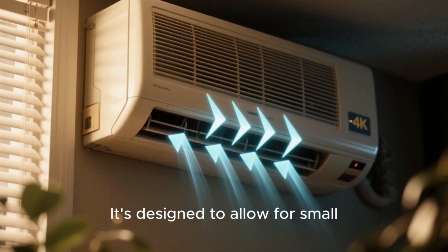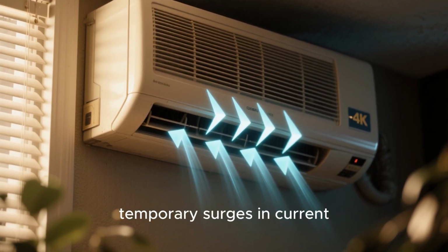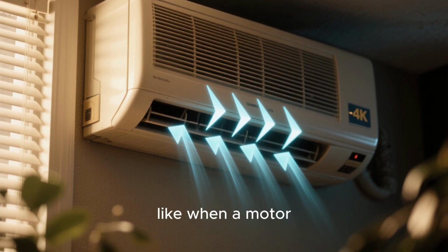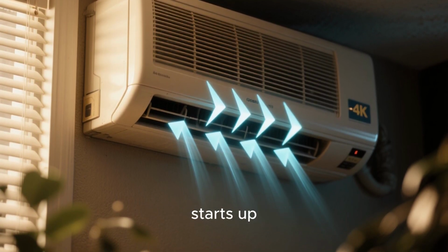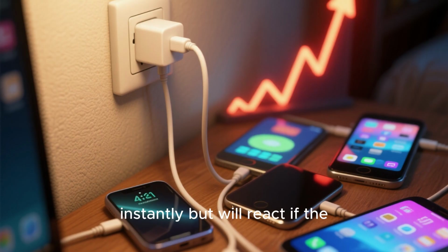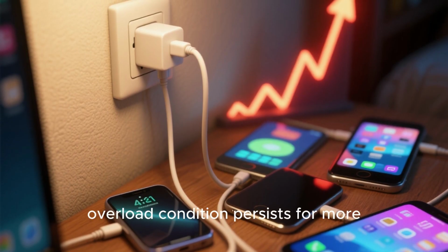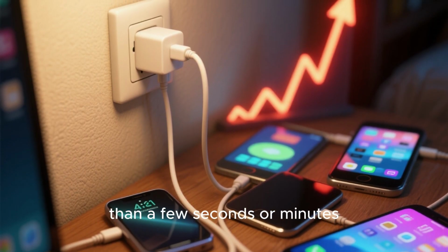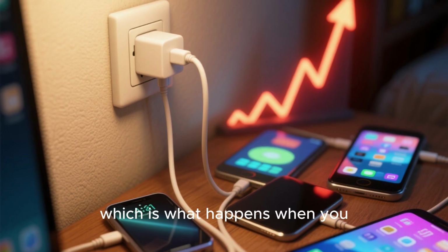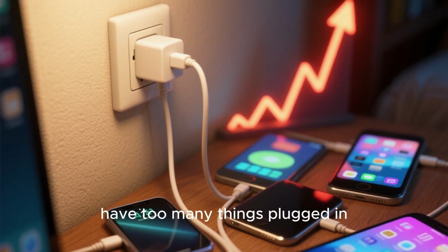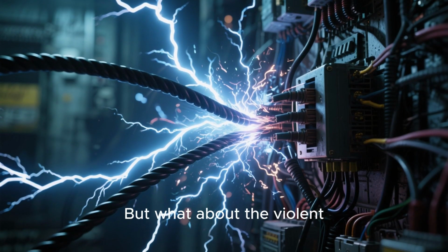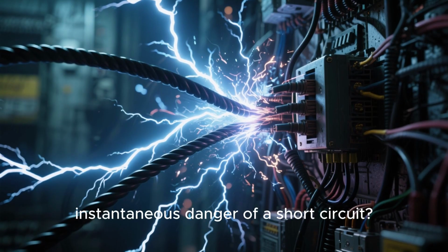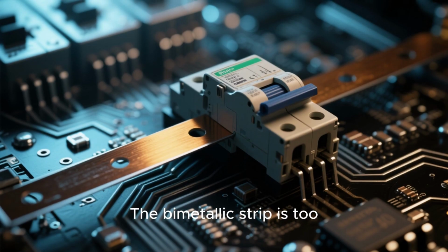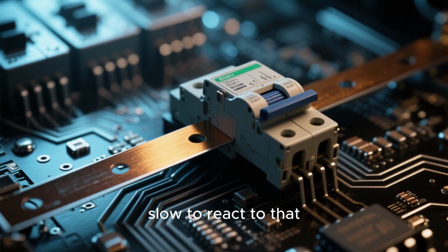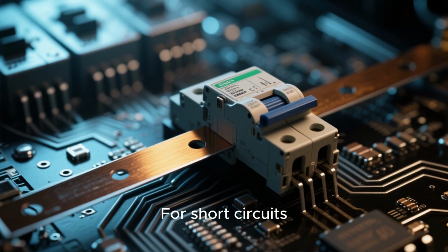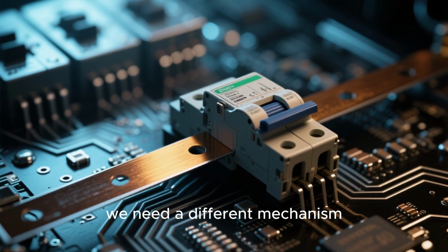It's designed to allow for small, temporary surges in current, like when a motor in your air conditioner starts up. It won't trip instantly but will react if the overload condition persists for more than a few seconds or minutes, which is what happens when you have too many things plugged in. But what about the violent, instantaneous danger of a short circuit? The bimetallic strip is too slow to react to that. For short circuits, we need a different mechanism.